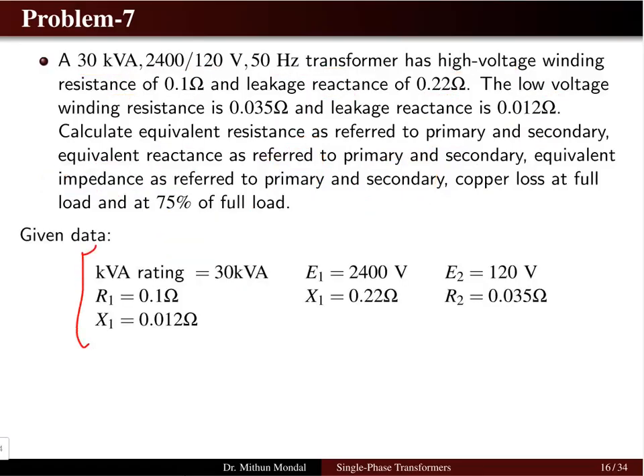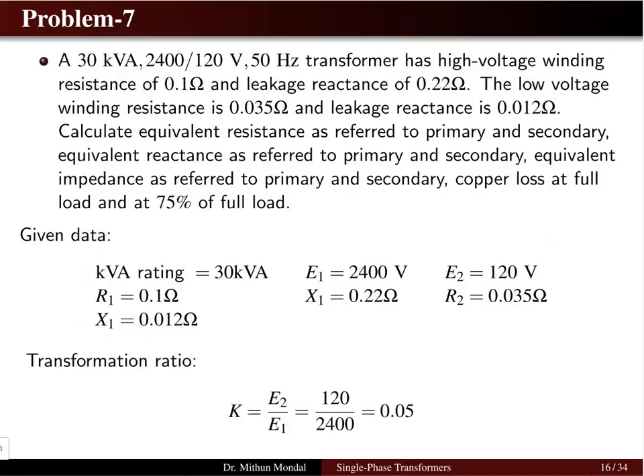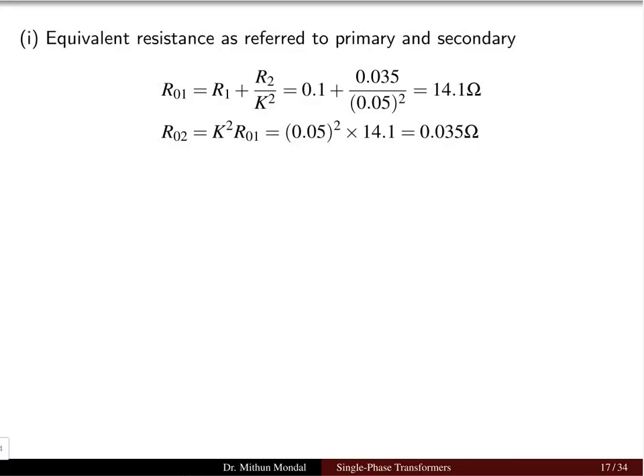So the kVA rating, the resistance of the primary, reactance of the primary, the induced EMF of the primary, induced EMF of the secondary side, the reactance on the secondary side and the resistance on the secondary side, all are given. So once we are noting these values, first we have to determine the transformation ratio K, which is equal to E2 by E1 comes to be 0.05. Now the resistance, first we will determine from the primary perspective.